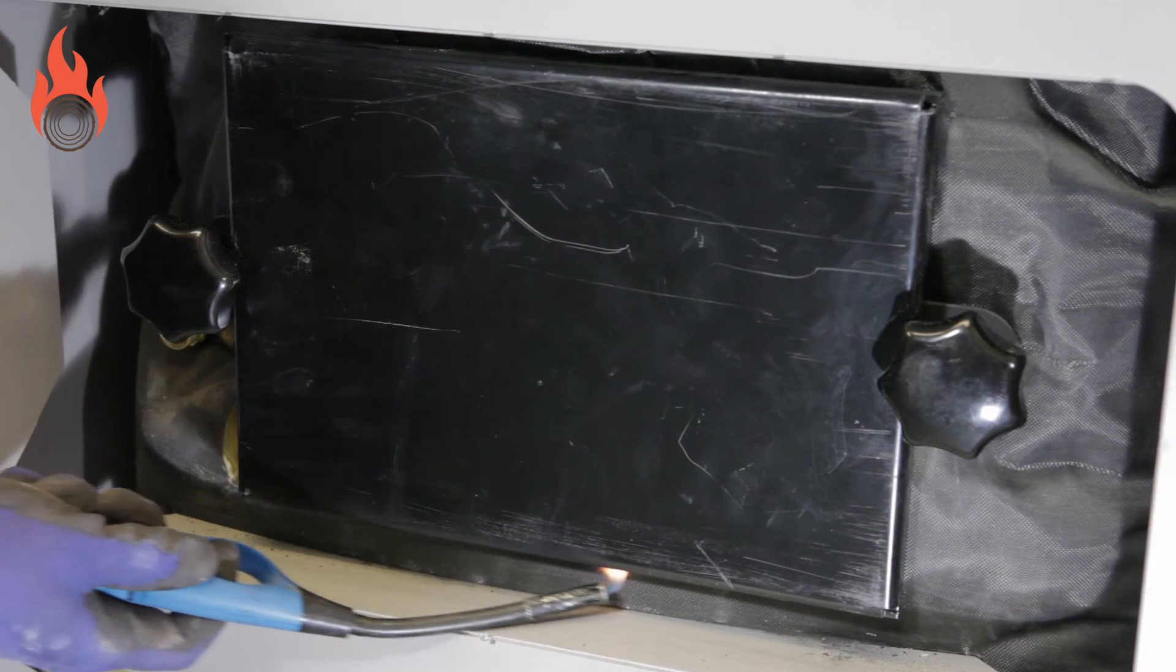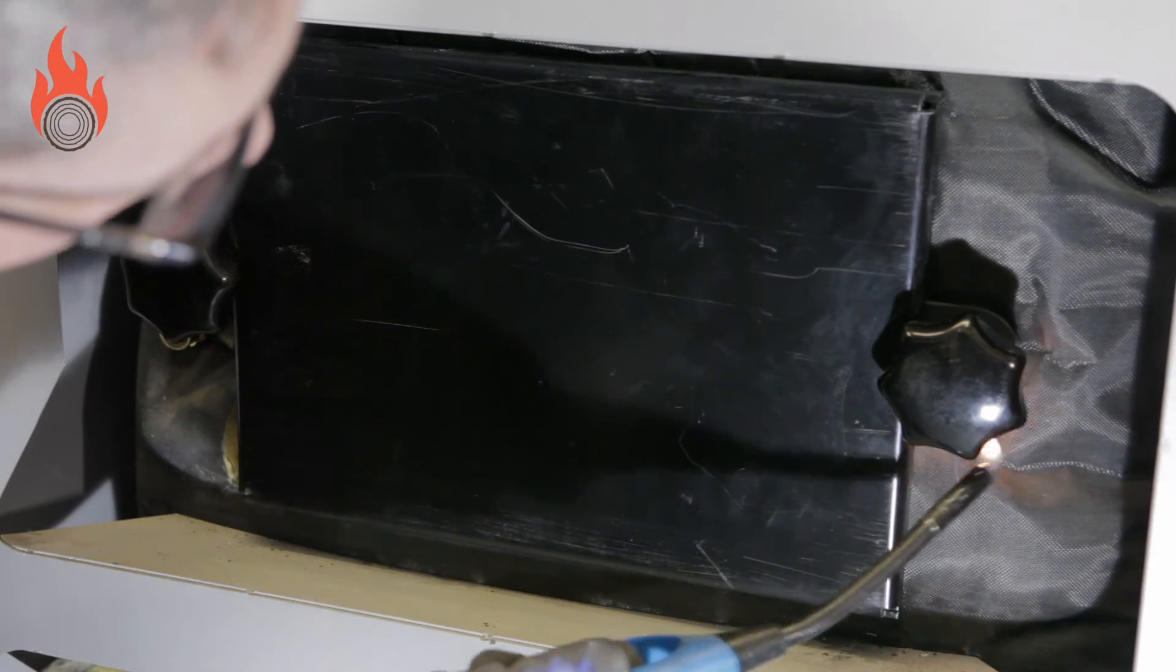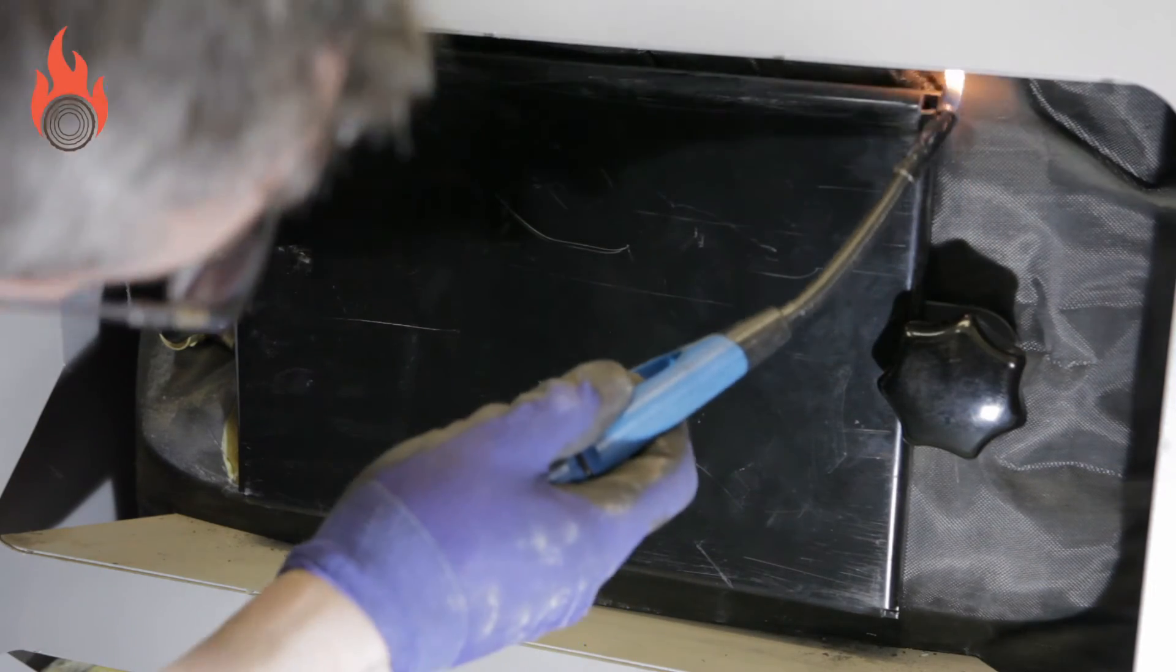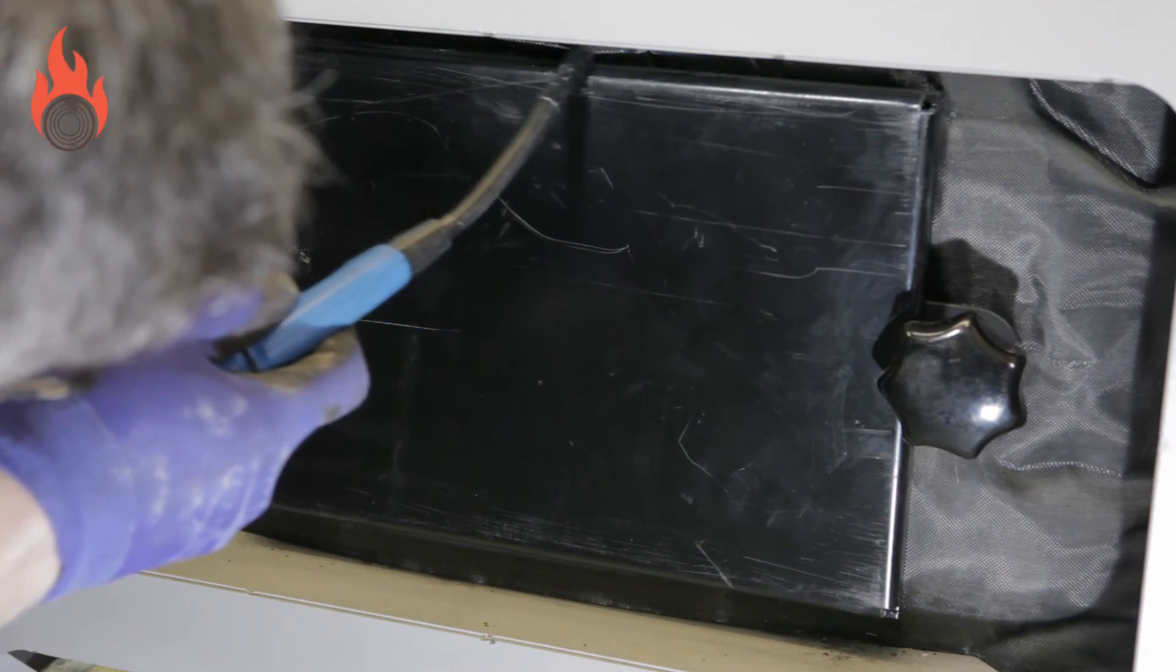If you then hold a lighter all around the door, you will see if the flame is being pulled towards the door or if the flame is stable. If the flame is being sucked towards the door, then the door seal will need to be replaced.